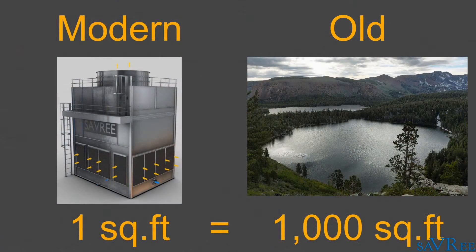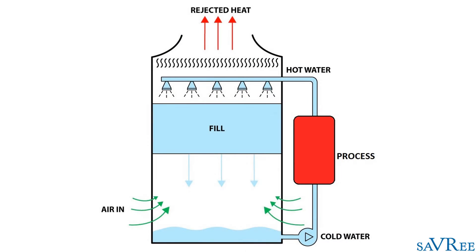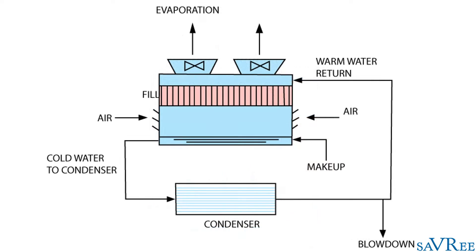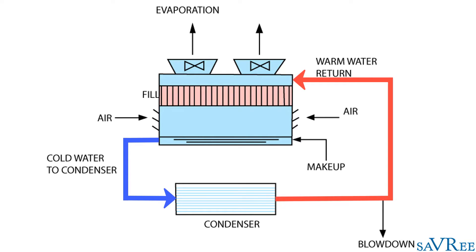Modern cooling towers require as little as one square foot of area to obtain the same cooling effect as 1,000 square feet of a natural heat sink. Additionally, water in cooling towers is recirculated, which drastically reduces operating costs compared to a once-through cooling system. This typical cooling tower arrangement shows water being taken from the cooling tower to a condenser, then back to the cooling tower. The cooling water temperature increases as it passes through the condenser and reduces as it passes through the cooling tower. The cycle repeats continuously.